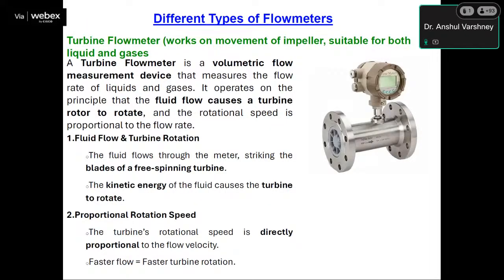A turbine flow meter is a volumetric type of flow measurement device that measures the flow rate of liquids and gases. It operates on the principle that fluid flow causes a turbine rotor to rotate, and this rotational speed is proportional to the flow rate. Basically, the fluid flows through the meter, striking the blades of a free spinning turbine. The kinetic energy of the fluid causes the turbine to rotate, so the turbine's rotational speed is directly proportional to the flow velocity.